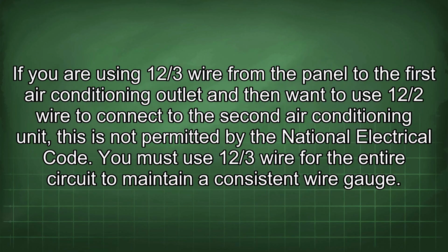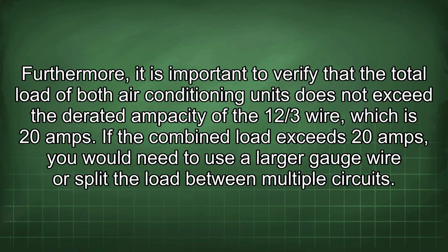Now let's consider the specific situation of wiring 2 air conditioning units. If you are using 12/3 wire from the panel to the first air conditioning outlet and then want to use 12/2 wire to connect to the second air conditioning unit, this is not permitted by the National Electrical Code. You must use 12/3 wire for the entire circuit to maintain a consistent wire gauge. Furthermore, it is important to verify that the total load of both air conditioning units does not exceed the derated ampacity of the 12/3 wire, which is 20 amps. If the combined load exceeds 20 amps, you would need to use a larger gauge wire or split the load between multiple circuits.